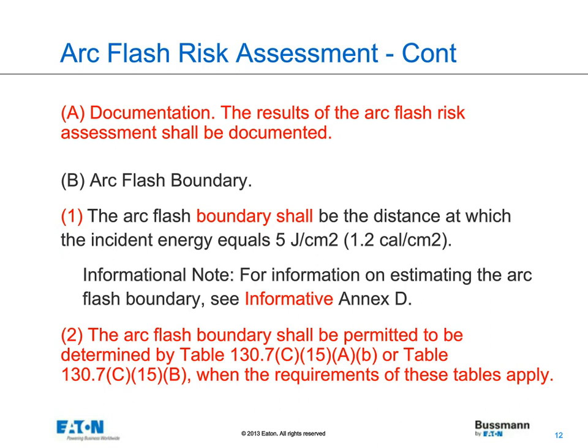And they added the informative. So whenever we talk about an annex, it's informative, which means it's not required to be followed. It's just there for information and guidance, but it's not mandatory to follow that. And then we added part two, which allows the arc flash boundary to be determined by the table method in lieu of calculation. So the boundary either can be calculated, and you would typically use the formulas in Annex D, or you can use the tables, and they will tell you what the arc flash boundary is based upon a given task.